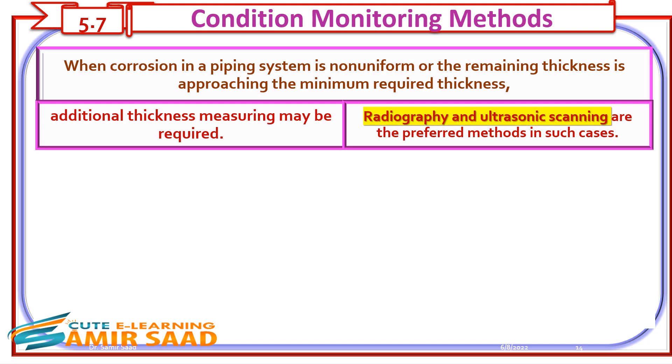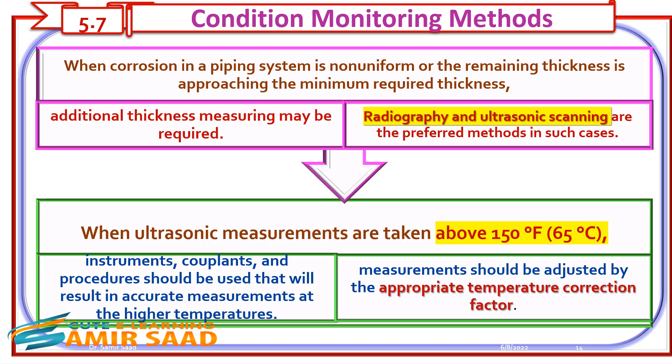When corrosion in a piping system is non-uniform or the remaining thickness is approaching the minimum required thickness, additional thickness measuring may be required. Radiography and ultrasonic scanning are the preferred methods in such cases. When ultrasonic measurements are taken above 150°F (65°C), instruments, couplants, and procedures should be used that will result in accurate measurements at the higher temperatures, and measurements should be adjusted by the appropriate temperature correction factor.